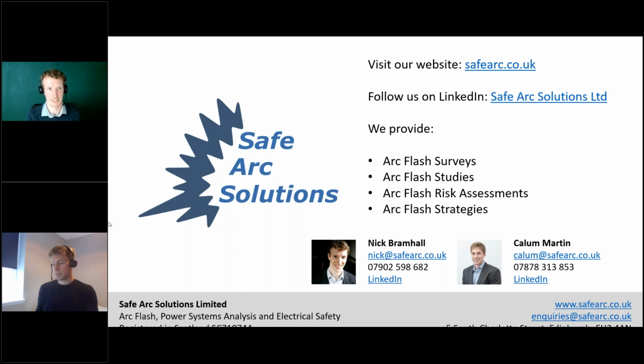An arc flash characteristically looks a lot like a short circuit, and that's where your overcurrent protection is looking after you. The best is to have instantaneous overcurrent protection, which gives you your fastest trip times. A lot of the dedicated arc flash detection devices are making the trip time as short as possible, often detecting the light flash from the arc flash and combining that with information about what the current is doing to get it tripped as quickly as possible. So I'd really say the focus is on your overcurrent protection rather than any other protective devices.